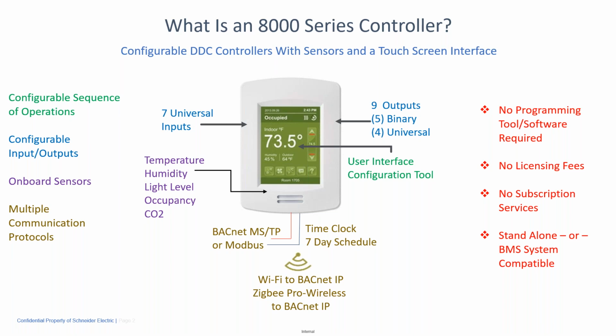All of the configuration is done through the user interface, through that color touchscreen interface. So essentially there's no programming tools, there's no software required to do this. You can basically take it out of the box, configure it for the piece of equipment, and you're off and running. Nice part about these controllers as well is there's no licensing fees, there's no subscription services. So what you pay for is what you get, and you don't have to add on anything else in order to make the controllers a functional piece of equipment as a standalone device or as part of a DDC system.